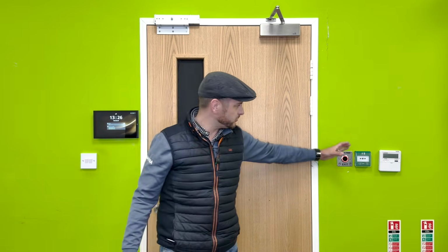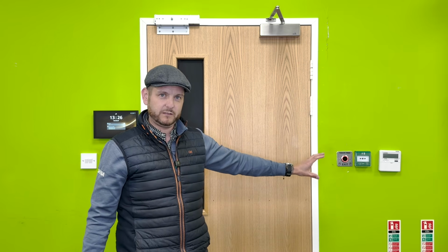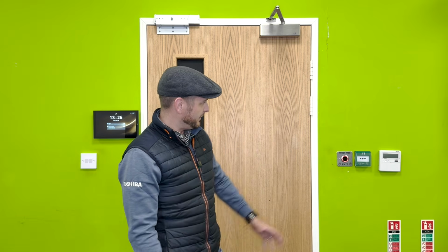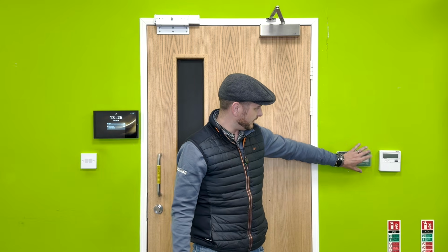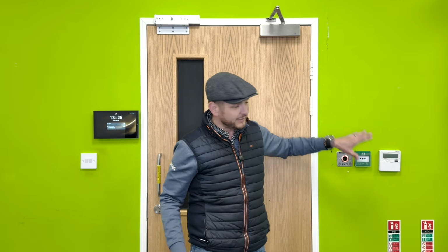Typically all doors will also contain a break glass unit. This allows you to get out of the secure area should a fire occur, and you have to put the door into free entry to allow evacuation, rather than the fire alarm triggering the whole fire system and all the doors opening. Typically they come with a cover which prevents accidental misuse, and they can be monitored to tell you when and where they've been pushed accidentally or, sadly, maliciously in some cases.